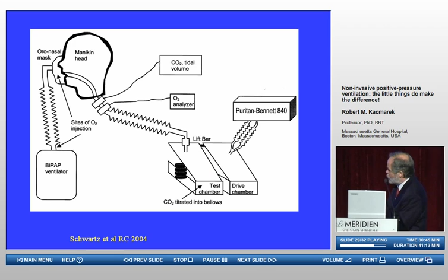The FiO2 was greatest if O2 was added into the circuit. So if the exhalation port was here, it was best to add O2 back at the ventilator itself and not close to the mask, allowing for a bigger reservoir of O2 during the inspiratory phase. Leak port in the circuit or a plateau exhalation valve, you got the highest FiO2 if you added O2 in the mask. In other words, if the expiratory port was here in the circuit, then adding O2 in the mask allowed it to accumulate in the mask in the short amount of rebreathed tubing and allowed you to get a higher FiO2. Although, when the leak port was in the mask itself, regardless of configuration, we had the lowest FiO2.